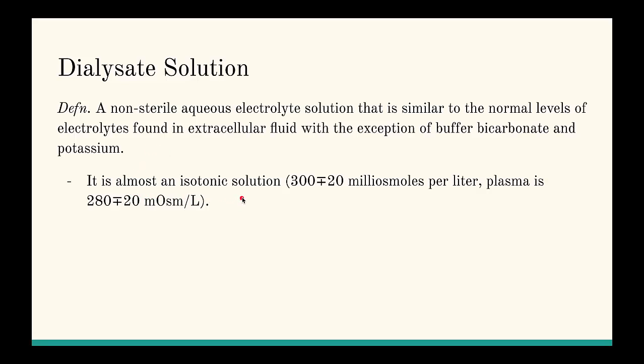There's also a note here. It is almost an isotonic solution, 300 plus or minus 20 milliosmoles per liter. Plasma is 280 plus or minus 20 milliosmoles per liter. So with this dialysate solution, what we want to pay attention to is that we want to put in a solution that is similar to the blood in terms of density. What I mean by density is, is it isotonic? If it's not isotonic, it's going to cause problems with your blood cells, such as red blood cells or other cells, because if you provide an environment that is hypertonic or hypotonic, you're going to have problems with the cells. They might burst. So that is one thing to keep in mind.